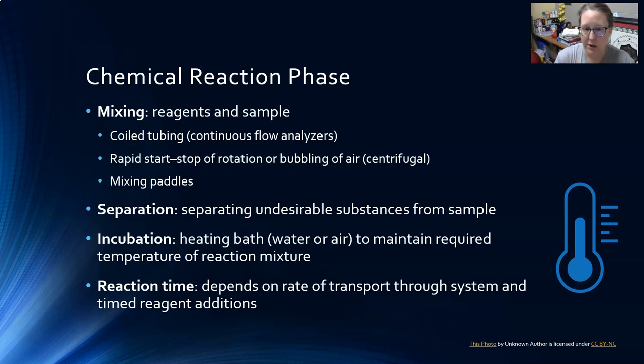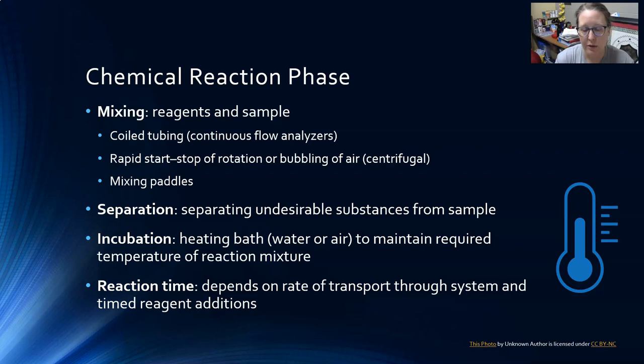This allows undesirable substances to be washed from the vessel. If incubation is required, which many reactions do need, the vessel goes through a heating bath of either water or air around the cuvette to maintain the required temperature — often body temperature or 37 degrees Celsius. Anything that uses enzymes in a reaction is very sensitive to temperature, so it's critical for the incubation module to be at the correct temperature.